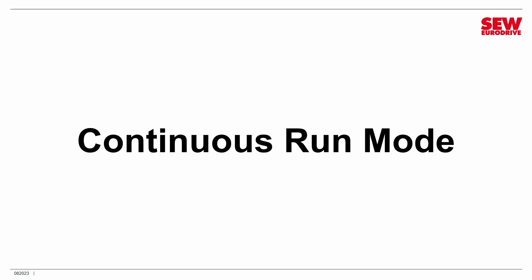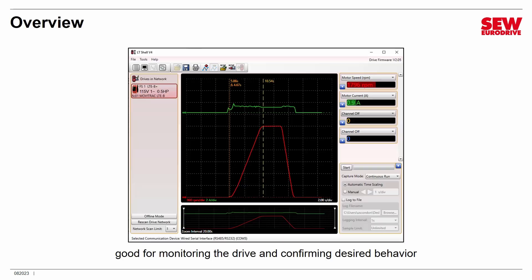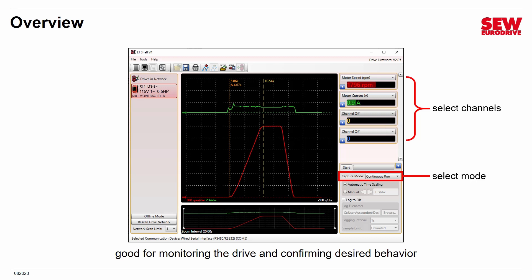Let's start by looking at continuous run mode — this is the easier of the two modes to set up and work with. This is good for monitoring the drive and confirming its desired behavior. The way you set it up is very simple: select continuous run under capture mode, select the channels you wish to monitor by assigning parameters to them. Here I've picked two channels — monitoring motor speed in RPM and motor current in amperes. Then you click the Start button and immediately data will start appearing on the screen. When you've captured enough information, click the Stop button, and then you can manipulate what's on the screen and take some measurements from it.